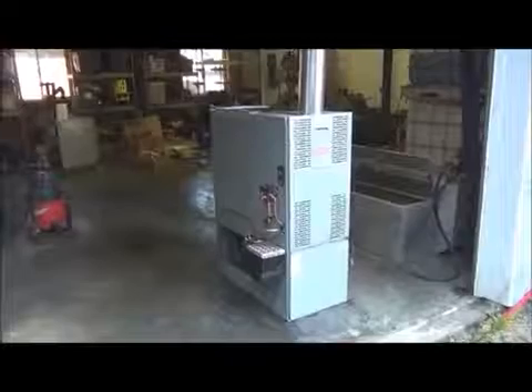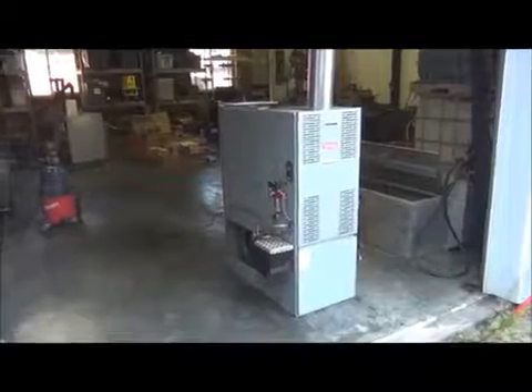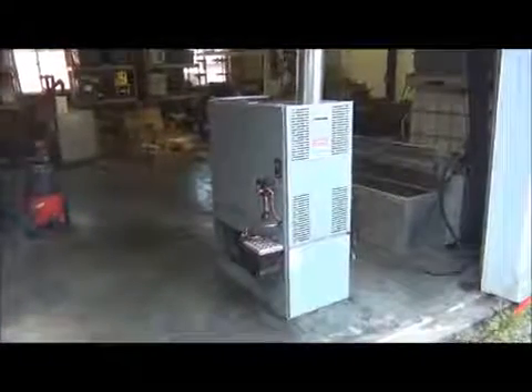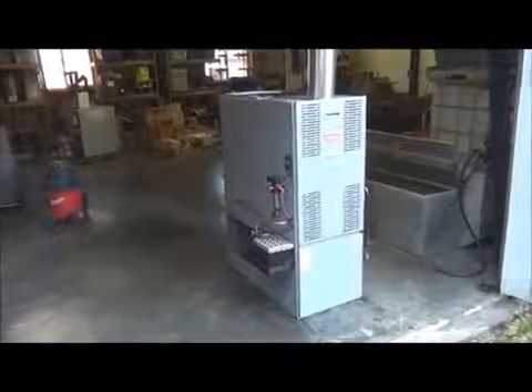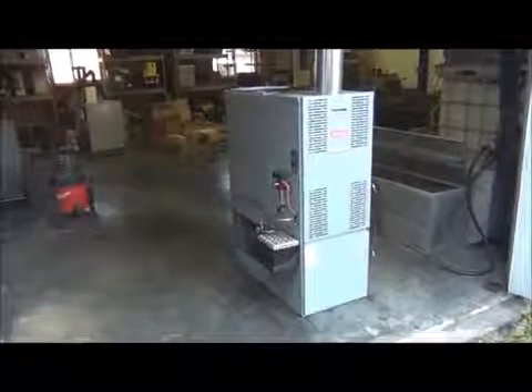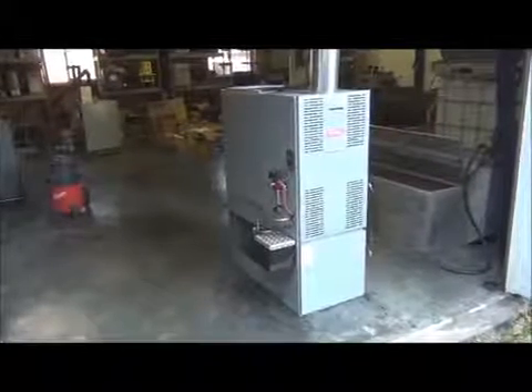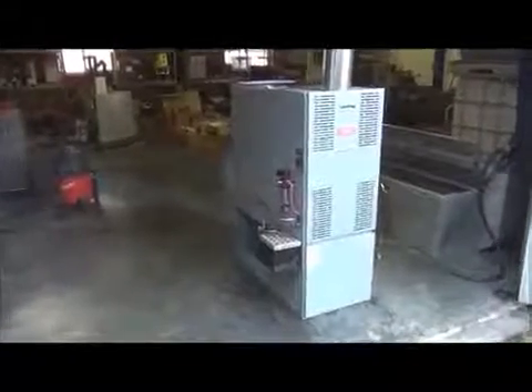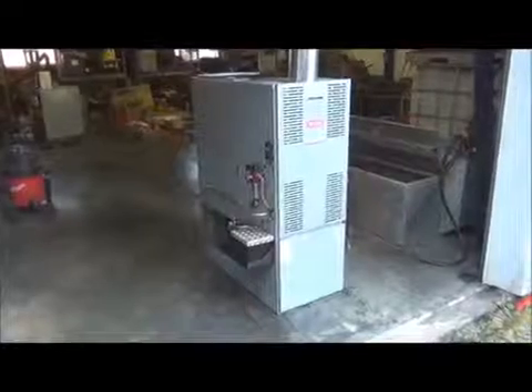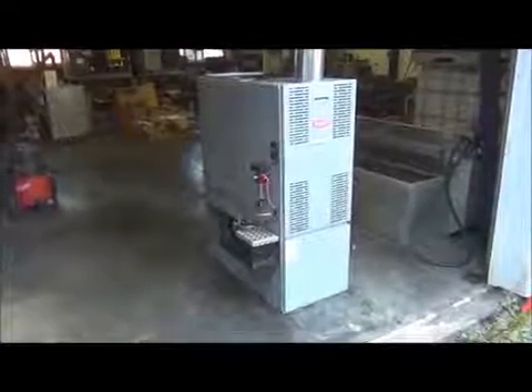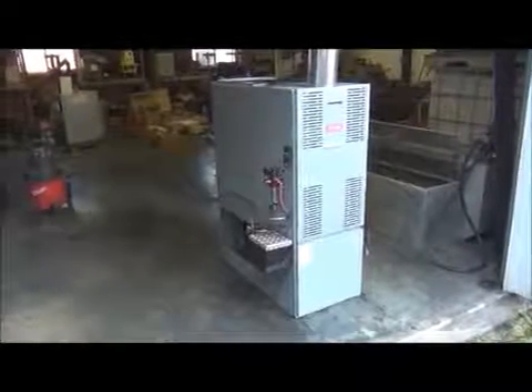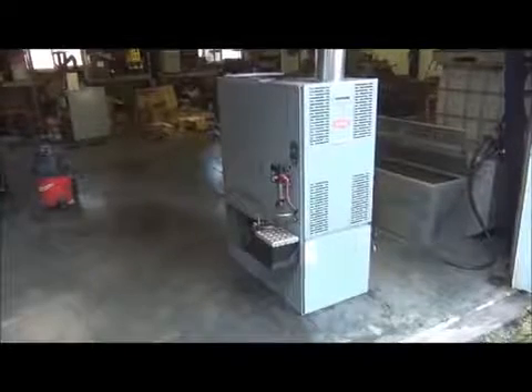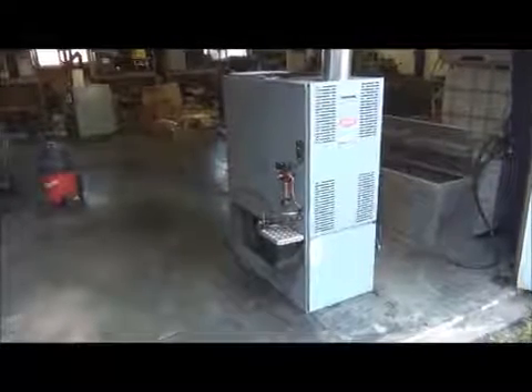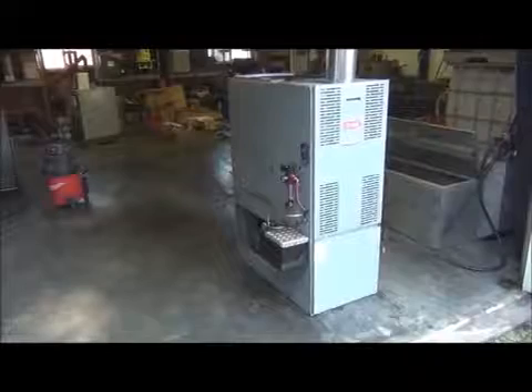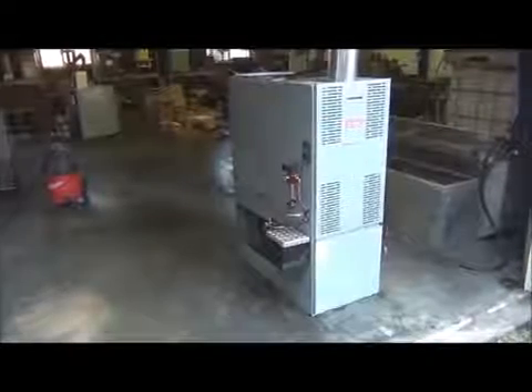Okay, what I have here is my latest waste oil furnace conversion. This one's based on a Bryant 127,000 BTU per hour oil-fired furnace. This was pulled out of a home that was converted from oil heat to natural gas. And this one I have set up to run on a variety of waste oil products. It'll run on waste motor oil, hydraulic fluid, transmission fluid, any kind of mineral oil like that. It'll also run on any type of bio oils like vegetable oil, peanut oil, or anything like that.